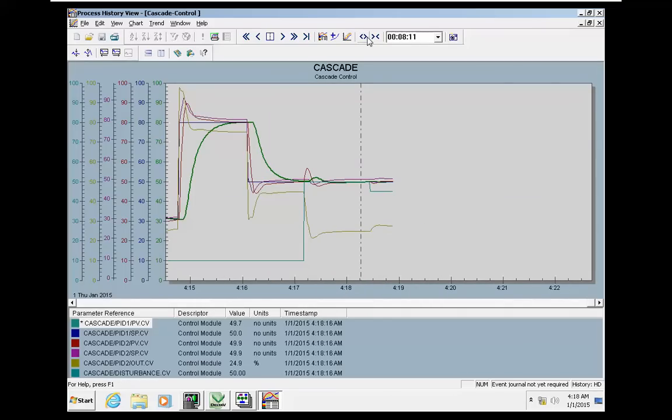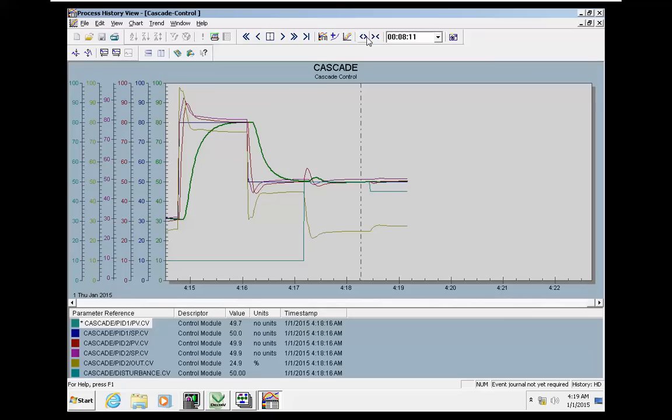So this is part 2. In order to summarize the disturbance effect: disturbance effect is mostly effective on the slave process. It hugely affects the slave process, and the effect on the master loop is very minor compared to the change in the slave.